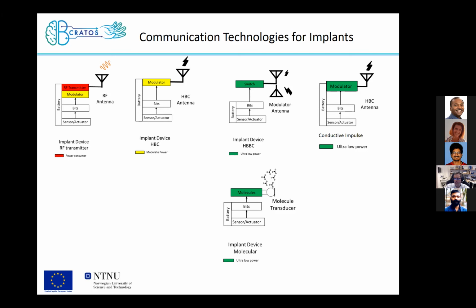The other part is the antenna. That is a part of the communication system. And usually the implants are very tiny and small. So we know from antenna theory that if the antenna size compared to the wavelength is quite small, the radiation efficiency drops very fast. But on the other side, if we increase the frequency, more loss in the biological tissues stops the communication. So there is a problem in this field.